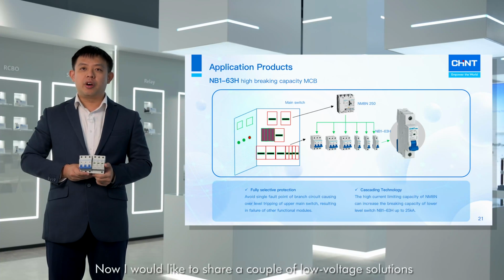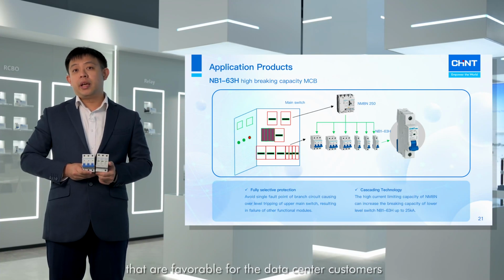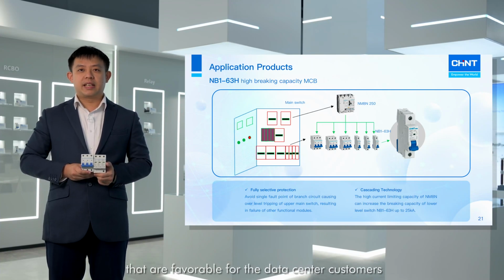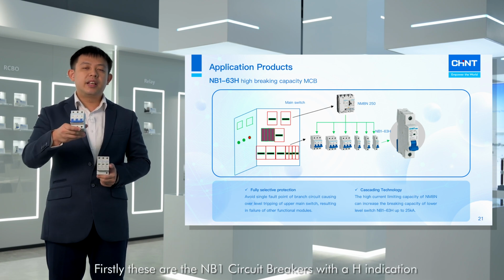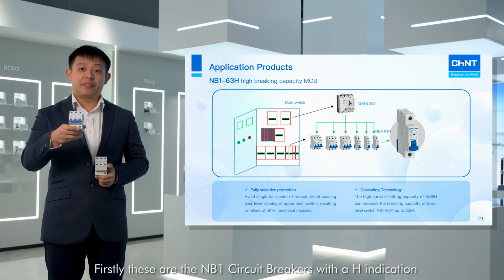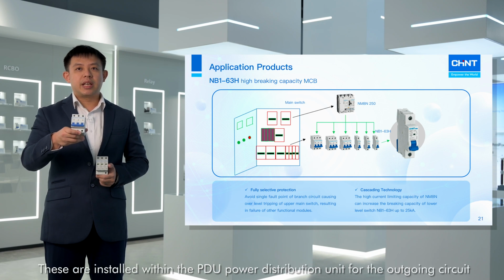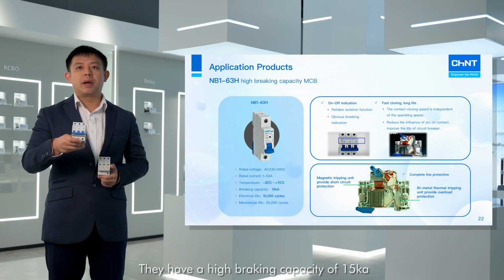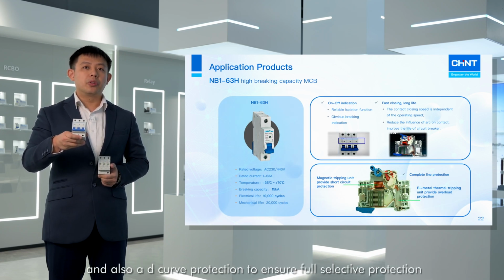Now I'd like to share a couple of low voltage solutions favorable for data center customers. Firstly, these are the NB1 circuit breakers with an H indication. These are installed within the PDU, power distribution unit, for the outgoing circuit. They have a high breaking capacity of 15 kA and also D-curve protection to ensure full selectivity.